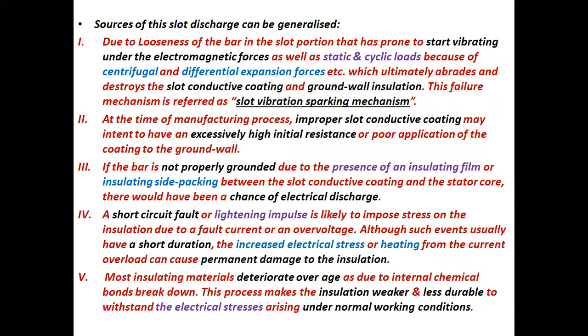Sources of this slot discharge can be generalized. One, due to looseness of the bar in the slot portion, which is prone to start vibrating under the electromagnetic forces as well as static and cyclic loads because of centrifugal and differential expansion forces, etc., which ultimately abrades and destroys the slot conductive coating and ground wall insulation. This failure mechanism is referred to as the slot vibration sparking mechanism.